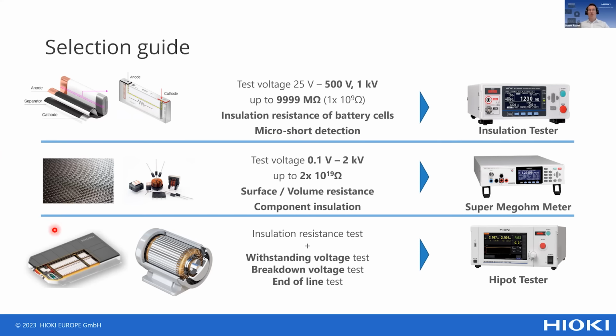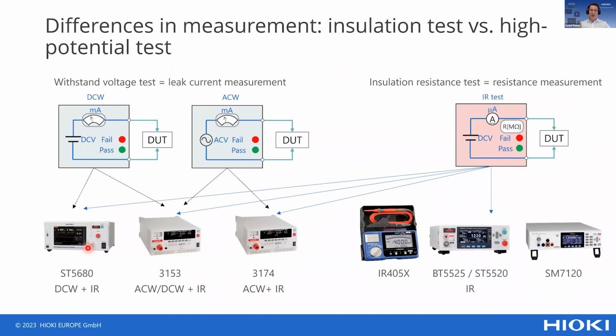So when you have the pack or the module, we would already suggest going to a high-pot safety test, because what you are interested in here is the insulation resistance of the battery cell inside, while with the pack, you are looking at the insulation of everything being assembled already. So it's a different approach, because again, one slide back, when you have the cell, rather the resistance value is of interest, while you have already seen on cell level the resistance value. You want to ensure that there are no leakage currents floating anymore, and therefore we would not suggest any longer the BT5525, but in this case ST5680.